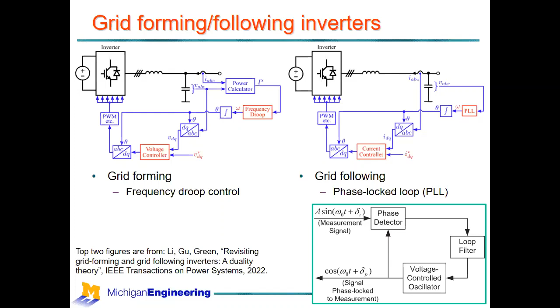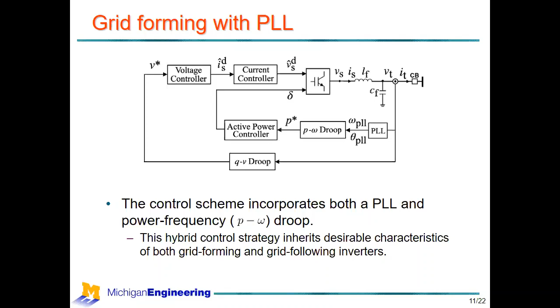So anyway, this is our particular control scheme, and I'll come back to various aspects of it. There's a measurement of the terminal voltage similar to grid following, a phase lock loop, which gives rise to the frequency and angle similar to grid following, but that then feeds through a droop characteristic to give it power. In grid forming, the power feeds through droop to give the frequency. In our case, the frequency gives rise to the power set point. Then there's an active power controller, and that drives the voltage here to give rise to the desired outcome. So it's a hybrid form of control. It takes both aspects into account.